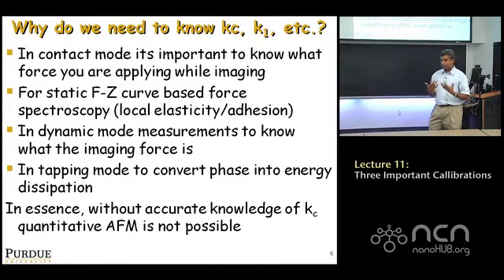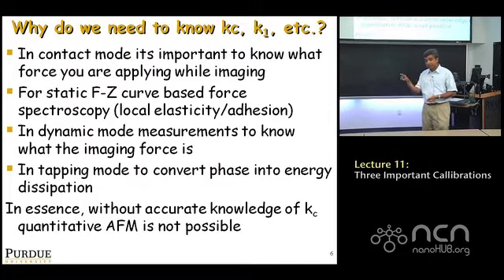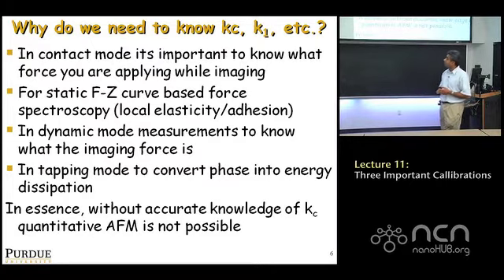So you have to measure forces in nanonewtons to know what regime of physics you're looking at, whether you have plastic deformations, you're elastic, or you're imaging the liquid surface as opposed to the real structure, and so on. The other thing is, whenever you try to measure local elasticity or adhesion, if you don't know the spring constant, you're not going to get a good number. You don't know what number you're getting, right? When we start talking more about dynamic mode, you need to know what forces you're applying as you're tapping on a sample. All these things require you to know what the spring constant K is, okay? So you cannot really do anything quantitative in AFM if you just report the force in terms of volts. You can't do anything quantitative with that, okay?